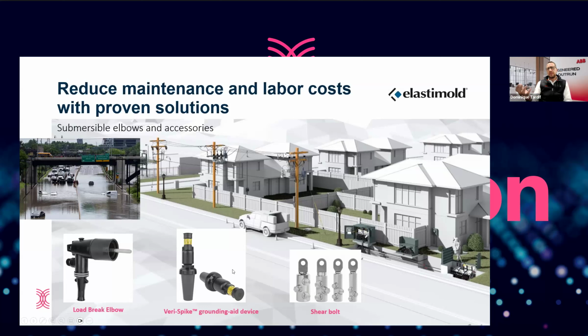Secondly, especially in adverse weather, installations like the shear bolt lugs you see here are easier. The normal lug is a compression lug, requiring specialized tools with a specific die for a specific lug on a specific conductor. That works fine in the lab or factory with conditioned environments, but not when you're knee deep in water, blowing snow, and rain. Shear bolt lugs instead take simple tools to put on, allowing many conductors to go into a common shear bolt lug with a simple tool to tie it in—so in cold, windy conditions, things go faster and you can get everything serviced more quickly.